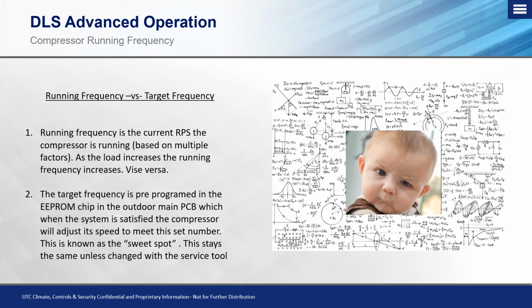And this is for 2 reasons. One of which is going to be maintaining a minimum flow to flush oil back through the system and into the compressor so that we don't starve it. This is also going to be at the sweet spot to maintain its energy efficiency, because we know with the inverter compressors, we can modulate the speed, and it's much more efficient to slow the compressor down and run at a lower frequency, or the sweet spot that we're talking about, than shutting the compressor off and turning it on, shutting it off and turning it on. Even with the inverter style, it's much more efficient to ramp it down versus off and on, like the traditional fixed speed system.